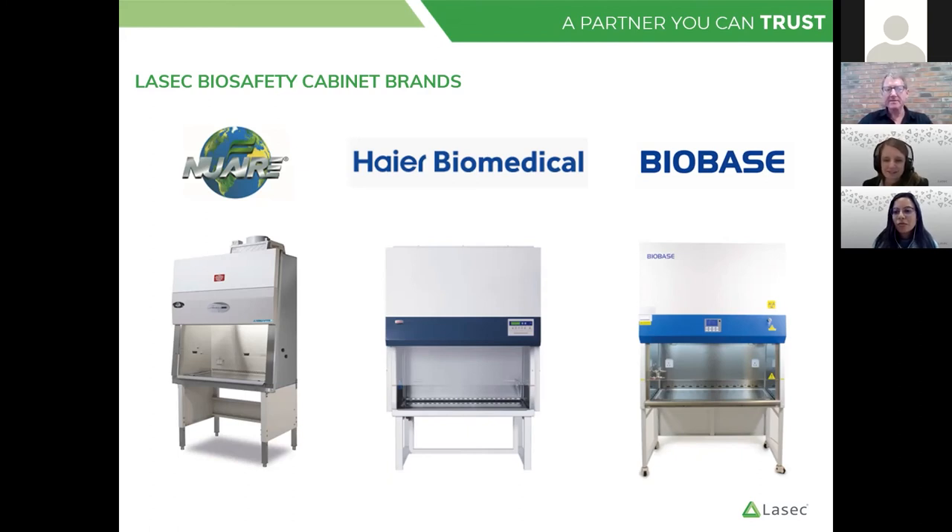The last question is: what are some of the daily maintenance things you should be doing with your biological safety cabinet? The main concern is to make sure it's kept clean — good laboratory practice as demonstrated in the video. It's not possible for the operator to do air velocity checks or HEPA filter checks. Of use would be the smoke pencil to do a daily test to make sure the airflow is okay.